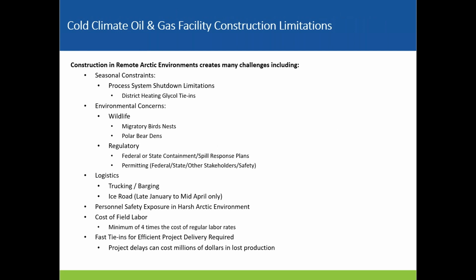Some things to be considerate of if you're doing a project on the North Slope are seasonal constraints. One approach to this would be your district heating glycol tie-ins. You obviously wouldn't want to break down your whole heating system dead of winter, so we're really limited in how we can deal with that. Environmental concerns can be a huge deal. You have a migratory bird on the way, and you stop a project for months. Had a polar bear den down in the well house just months ago. That was a big stir up on the slope. A lot of regulatory requirements put on us, federal and state, spill response perspectives and permitting.